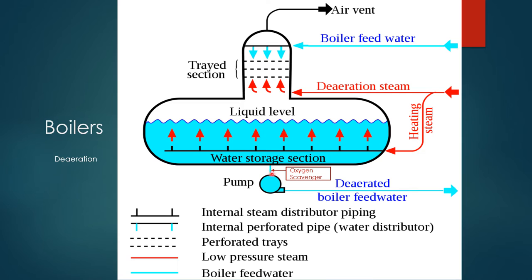The level in the deaerator is maintained at around 50%. The two outlet headers are collected into a single line. At the outlet line immediately after the storage section, the oxygen scavenger is injected. The pump suction maintains around 1.4 to 1.6 bar (1.5 bar), so even at 106 to 108 degrees centigrade, water vapor will not form, avoiding vapor lock or cavitation in the boiler feed water pump. The deaerator situated at 14 to 15 meter height provides sufficient NPSH to avoid cavitation. This outlet feeds boiler feed water to the boiler.